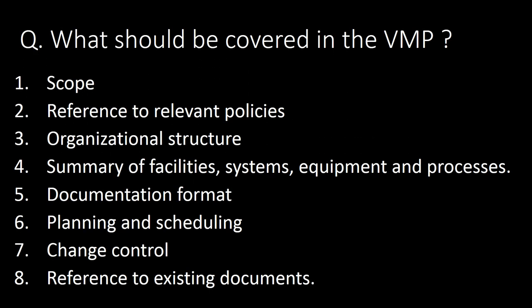An important question is: what should be covered in the VMP? The VMP should cover scope, reference to relevant policies, organizational structure, summary of facilities, systems, equipment and processes, document format, planning and scheduling, change control, and reference to existing documents.